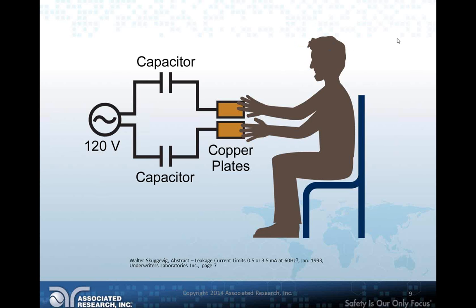Also, most high-pot tests, or high-potential dielectric withstand tests, since your products run at 50, 60 hertz, you got to run your test at 50, 60 hertz, which ups the danger because in those cases you're dealing with a much higher voltage. So I just wanted to give you guys a little background on where they got those numbers in that table we were looking at.